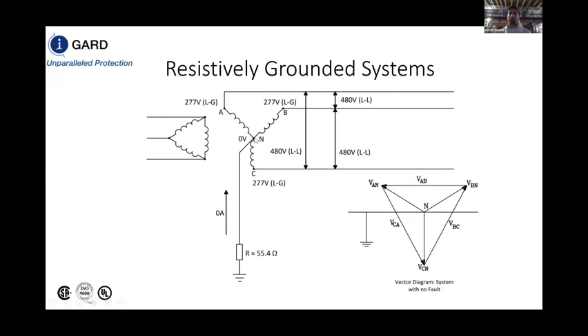Our neutral gets elevated to the line to neutral voltage of the system at 277 volts, line to neutral. And our unfaulted phases will get elevated to 480 volts, line to ground. This will effectively give us 480 volts line to line to continue our process, even with respect to the faulted phase and the unfaulted phases. So at this point, we haven't really tripped anything. We've experienced our first phase to ground fault, and we're limiting that fault current to a specific value.